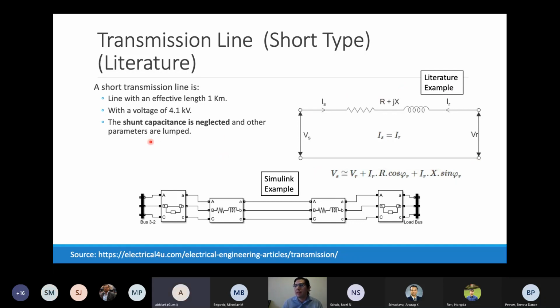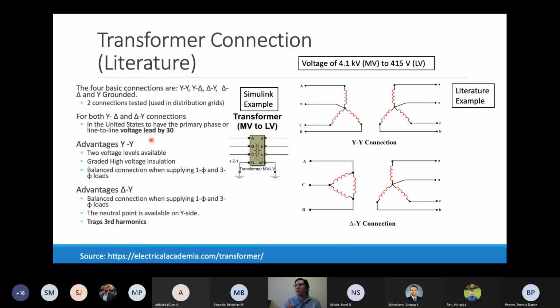And the shunt capacitance here is neglected due to the length of the line, because we are working in short type line mode. For our transformer connection, we know there are different types of connection between YY, Y delta, delta delta, Y delta, and also Y grounded modes. So we are trying to utilize the most common ones seen in distribution levels, which is basically delta Y and Y to Y. Delta Y is far better because it traps the third harmonic in case we have some faults. So we tested both, critical for our case study.